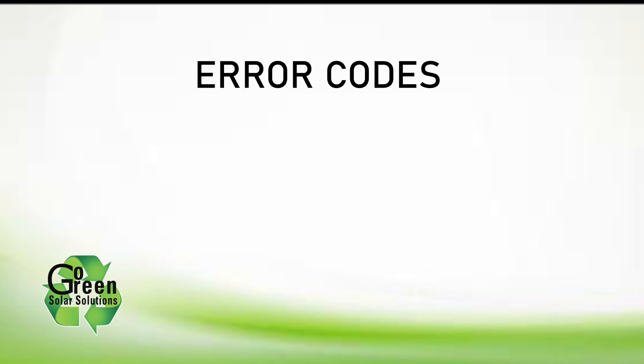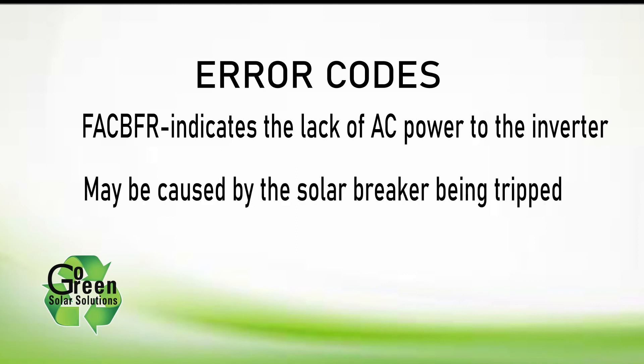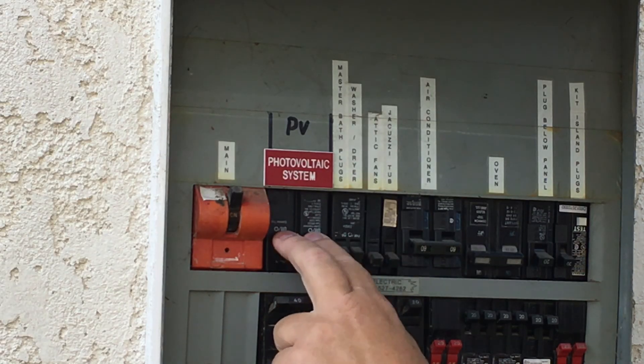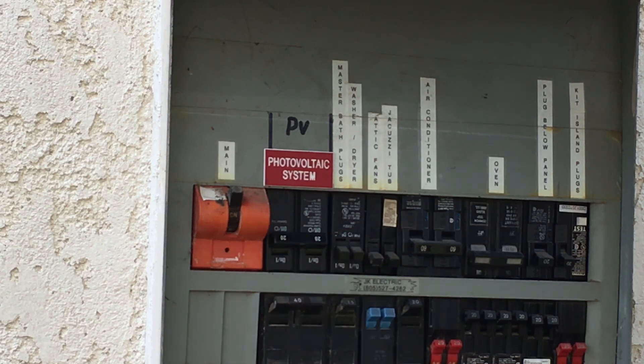You should also check for error codes on the inverter display and write them down. FACBFR is a common error code that indicates the lack of AC utility power to the inverter. The most common cause is that the main electrical panel solar breaker has tripped. To reset, turn the breaker off and back on again — that often solves the problem.